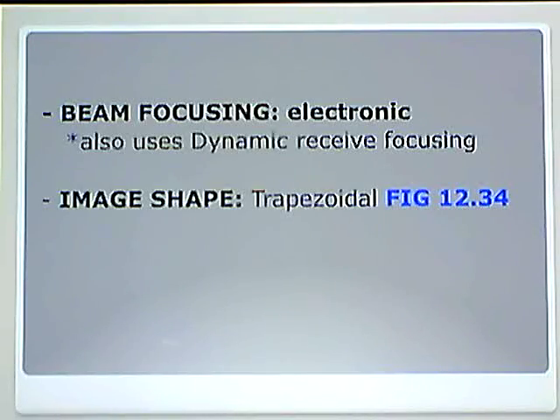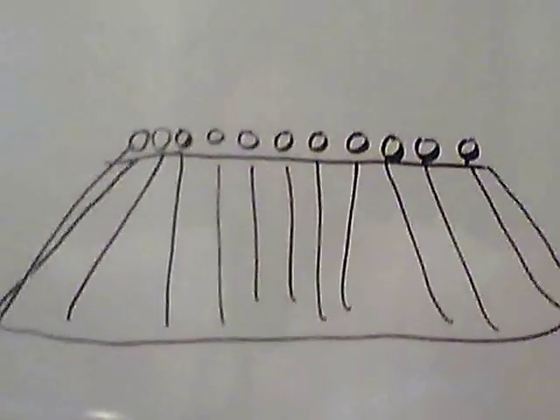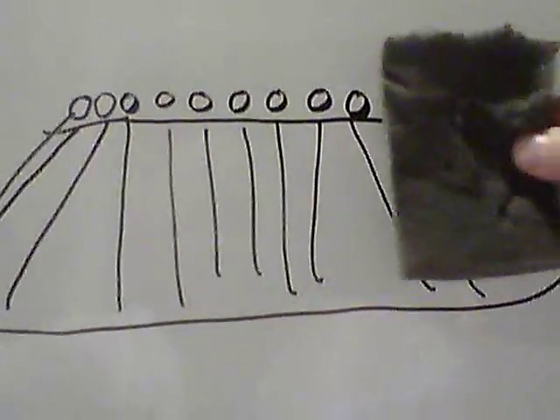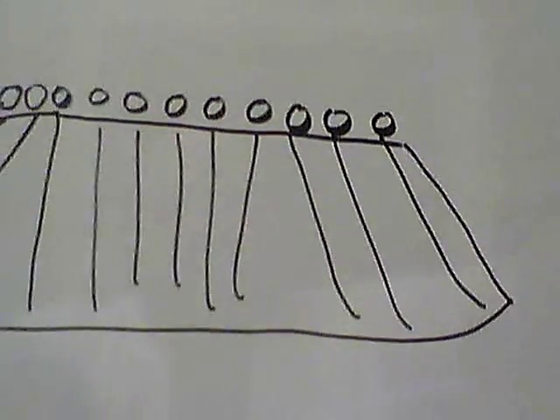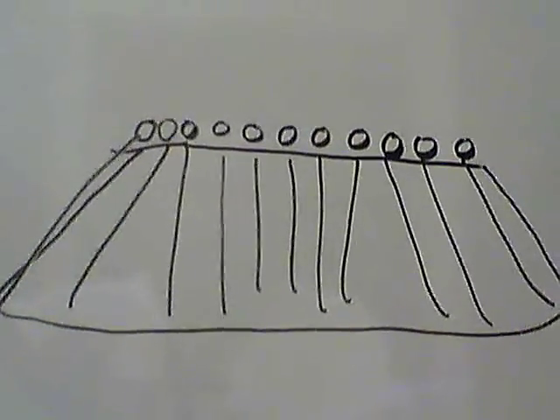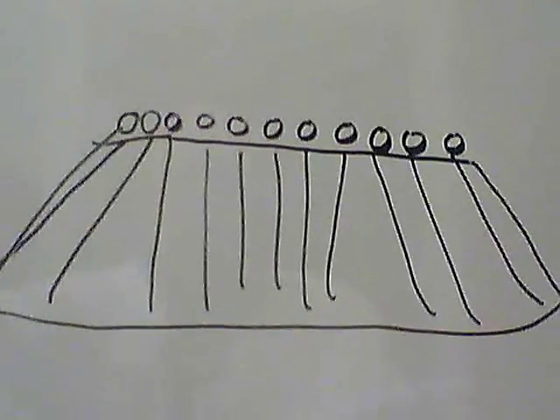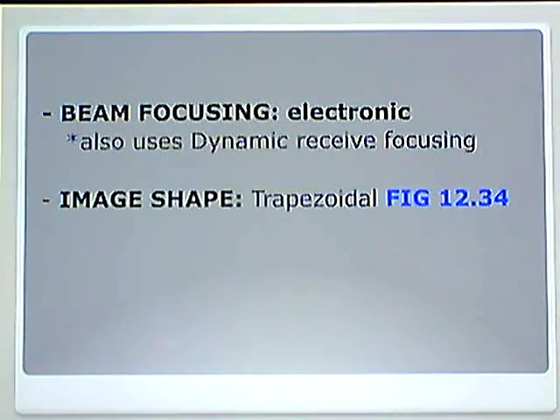Beam focusing is electronic. It also uses dynamic receive focusing. The image shape is trapezoidal. Again, this is why: because I am no longer steering straight down. I'm steering out to the side and out to the side, and I get a wider image on both sides of the rectangle, hence trapezoidal. That's the question I'm going to ask you. Vector array transducers create what shape image? Trapezoidal. Beam focusing is electronic.